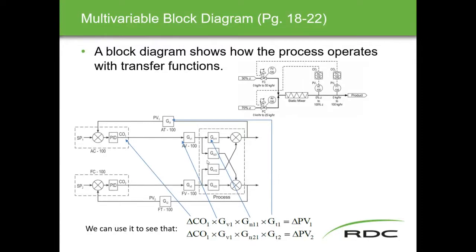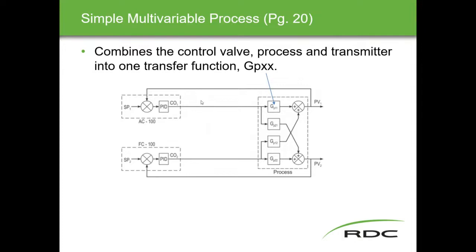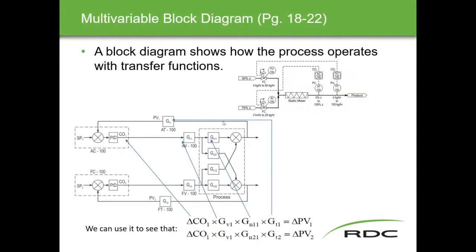The signal also comes out of controller one, goes through GV1, splits off, and goes to GN21 — the decoupling value that gets summed with the signal from controller two in order to get rid of the interaction. This multiplier adjusts the signal, multiplies it by this value, and puts it into the summing block so that when it gets added together it doesn't change its process variable. The signal goes through GN21 into the summing block, through the transmitter, gives us the new process variable, and then back to the controller.